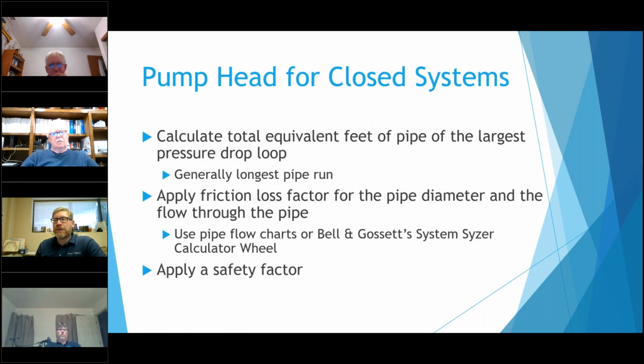So, the way they go through an actual calculation for the pump head in a closed system, they basically follow the one loop. You don't actually add every single pipe loop. You just want to pick the one that has the longest or the highest pressure drop. Generally speaking, it is the one with the longest pipe run, because that loop is the longest and therefore it's trying to shove so much water through that pipe. So they add up all these equivalent feet of pipe length, and you've got elbows and valves. Where the pipe is 1, the valve might be 3, the elbow could be 4 or 5, depending on what type of elbow you're using.